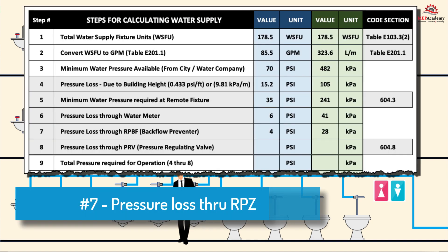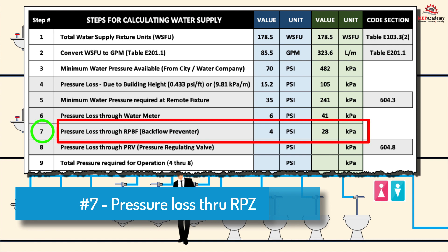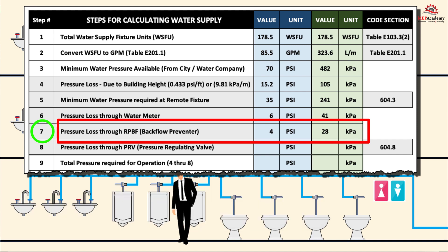Step 7: Pressure Loss Through Backflow Preventer. A reduced pressure backflow assembly (RPZ) is used to prevent dirty water from reversing flow and contaminating the clean water supply. If required, the pressure drop must be included in the total pressure loss calculation. In our example, the pressure drop through the backflow preventer is 4 PSI or 28 kPa.